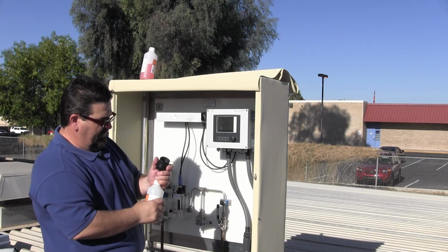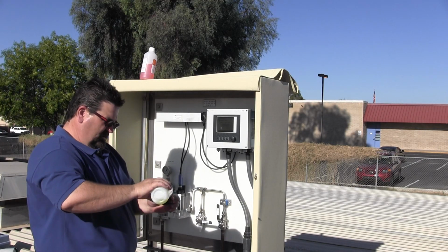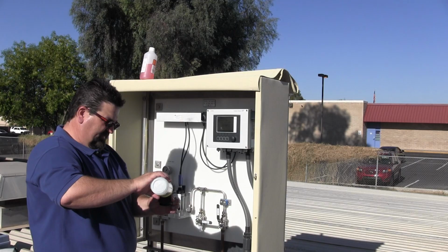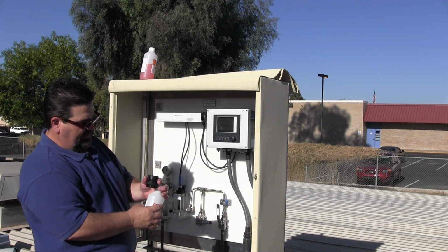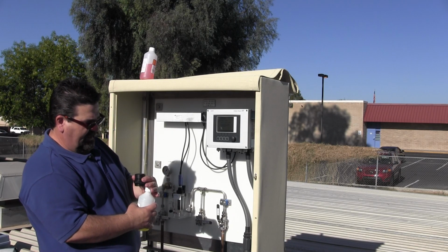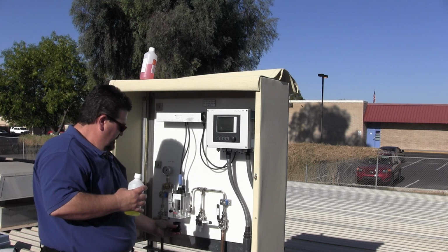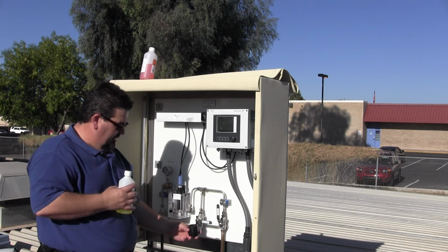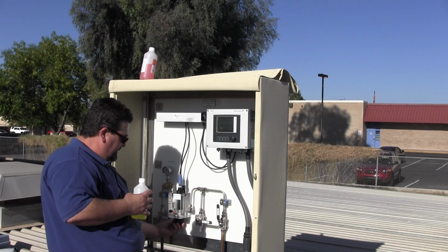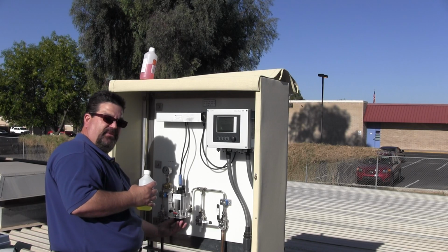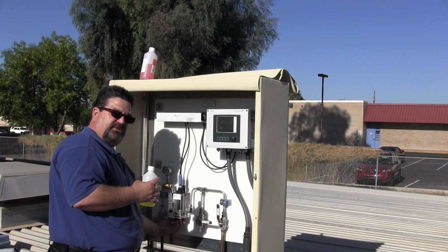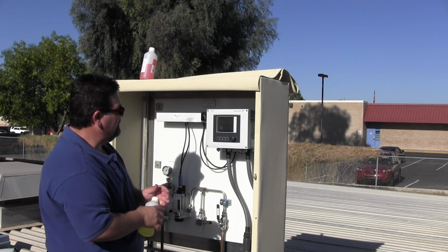We're going to use a 7 buffer here. We're going to fill the cup up about 2/3 of the way, and there's actually a little line in there that kind of gives you an indication of how full you need to make it. With the deep side of the cup up, we put it back into the flow block and just tighten it up a couple of threads. Now the pH electrode is immersed in the pH buffer.